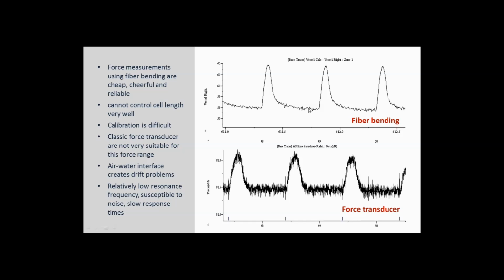But the trouble is, it's hard to control the exact length of the cell, and what is worse, they're difficult to calibrate. You can use another force transducer to calibrate them, but it turns out the results are quite variable, so you never quite know the exact force level. But it still makes it a great choice for stretching the cells and getting relative force changes. So we decided to put in an existing force transducer, but of all the force transducers that are available, this is the one from Aurora, and we thought this was the very best there is. This is a very good force transducer, but we are operating at the bottom 0.5% of its range, and it's just not designed for that. So the signal-to-noise ratio suffers.